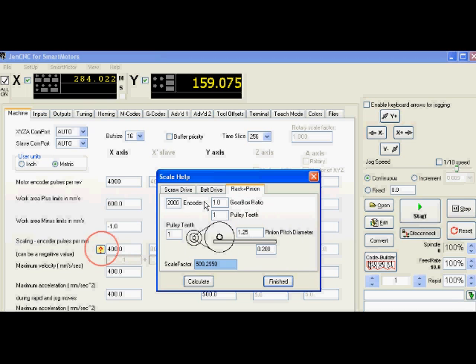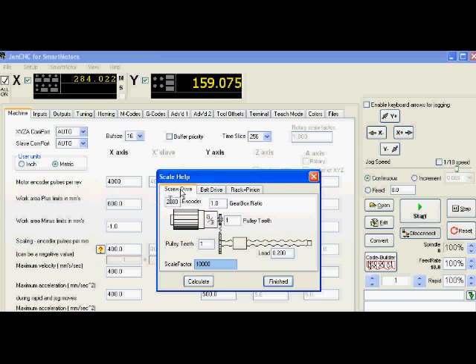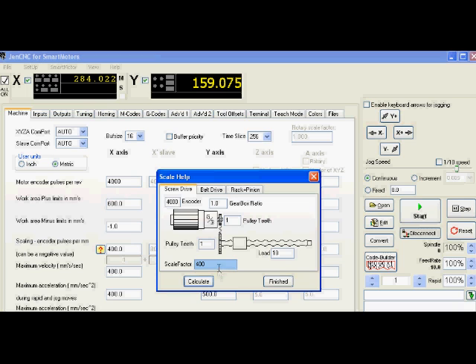For instance, if I go to screw drive tab, I put in 4000 encoder counts and I put a lead of 5 millimeters and hit calculate, a value of 800 will come back. If I do the 10 millimeter lead as I have set up now, a value of 400. That 400 is what I put into that scale factor. So I click finish.